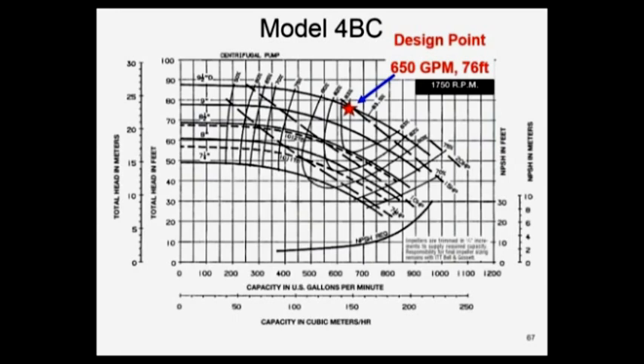Perfect. By the way, we're about 83% efficiency, not a bad looking little pump. That's what's specified. That's what we got. That's what's on the drawings.